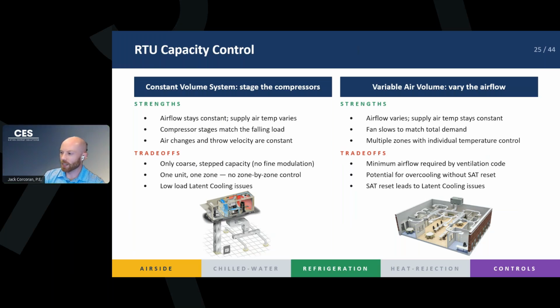And as soon as it gets too warm, then we're going to open up our damper, allow more airflow in, and that'll cool down our space, right? So this is very powerful. You can have dampers in individual zones, right? Our VAVs are going to be for a group of offices, an individual office. Every zone is going to be able to modulate the temperature in real time. You're going to be able to get multiple zones, all with diverse loads, satisfied with this system.